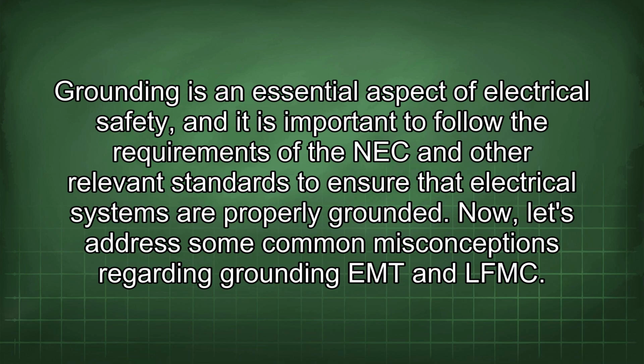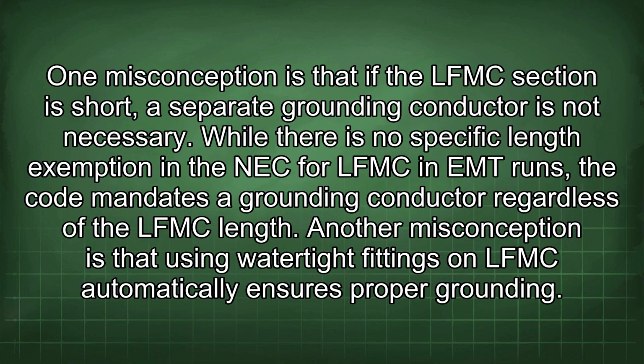Now let's address some common misconceptions regarding grounding EMT and LFMC. One misconception is that if the LFMC section is short, a separate grounding conductor is not necessary. While there is no specific length exemption in the NEC for LFMC in EMT runs, the code mandates a grounding conductor regardless of the LFMC length.